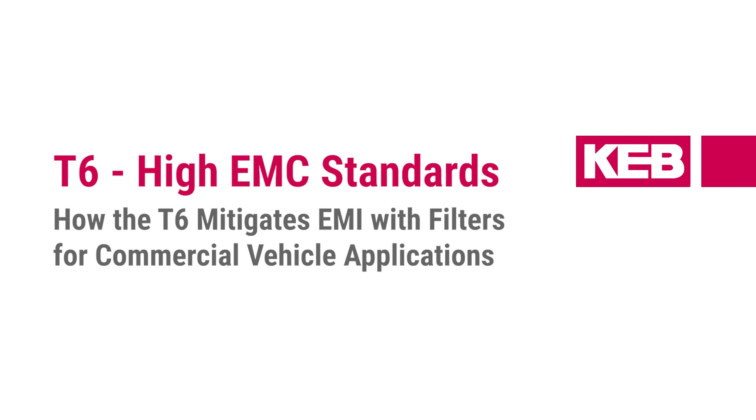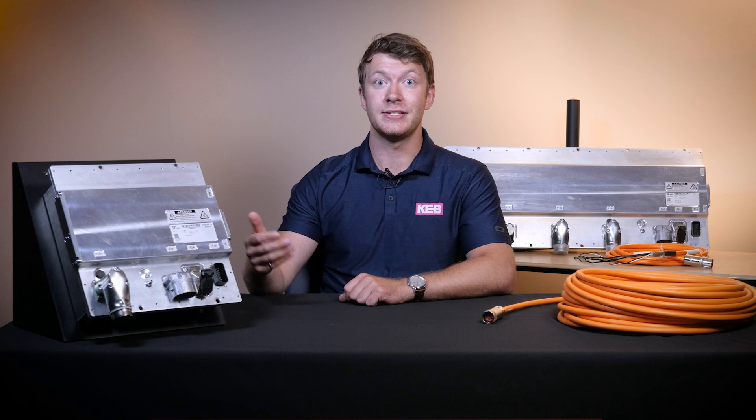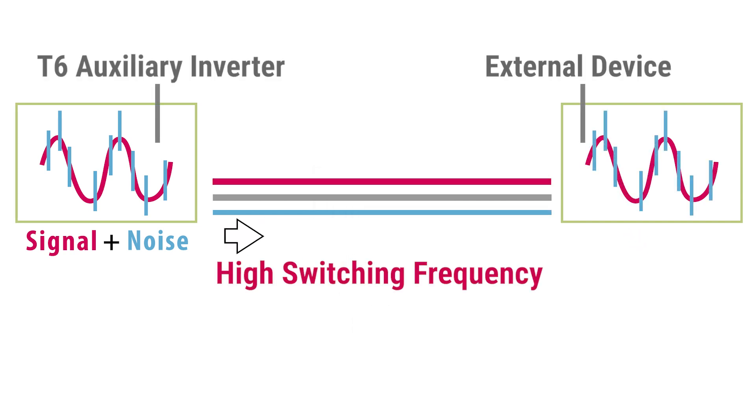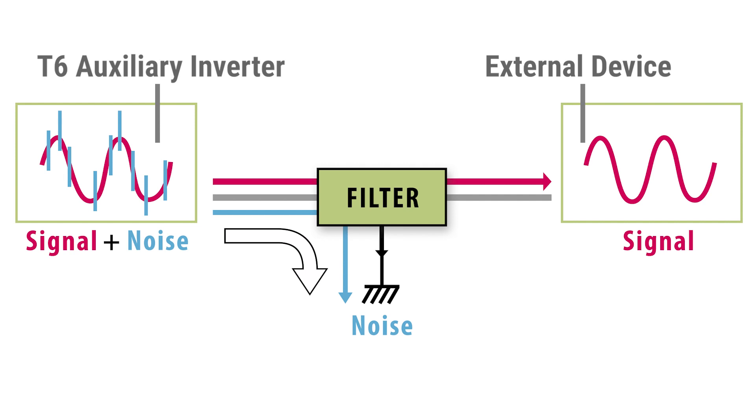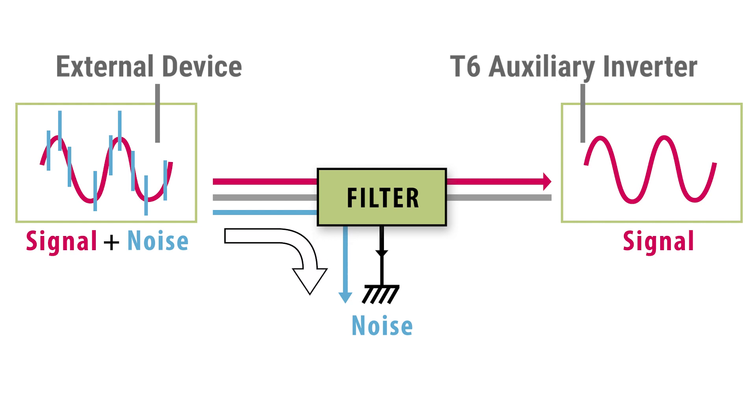The T6 addresses EMC with various strategies. The first of these is integrated DC EMC filters. These filters are designed to mitigate conducted emissions. They protect external devices from the high switching frequencies within the inverter, making sure those aren't conducted out, and the T6 uses those filters to prevent external noise from coming into the inverter.